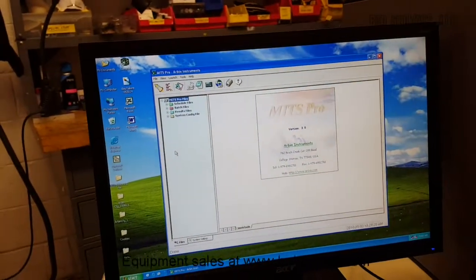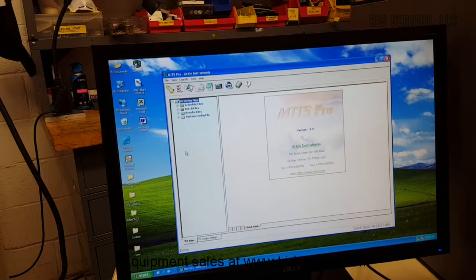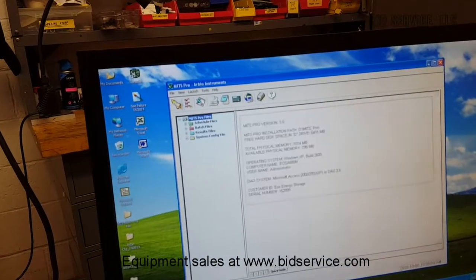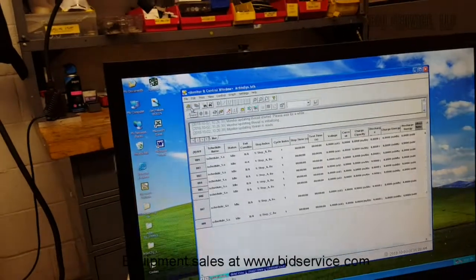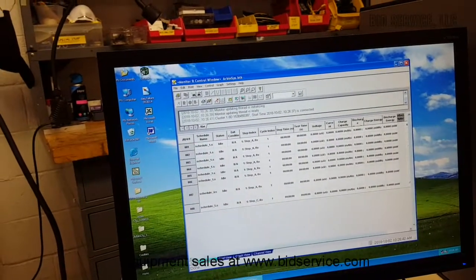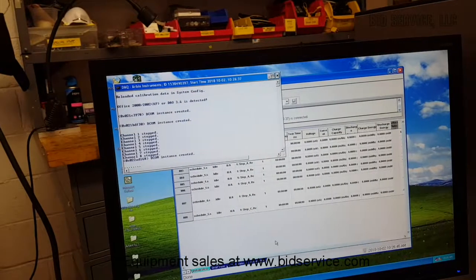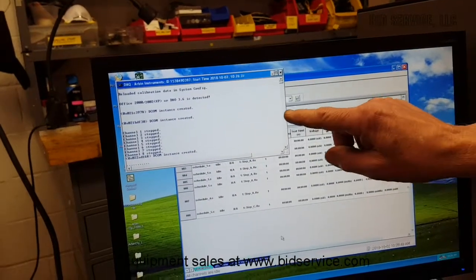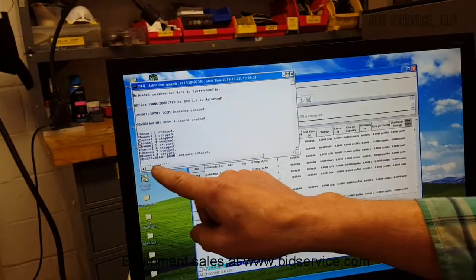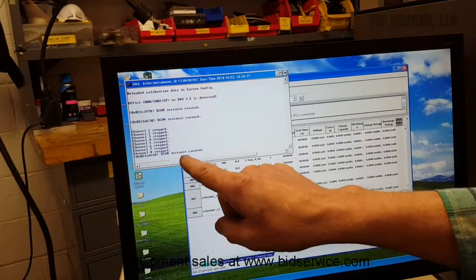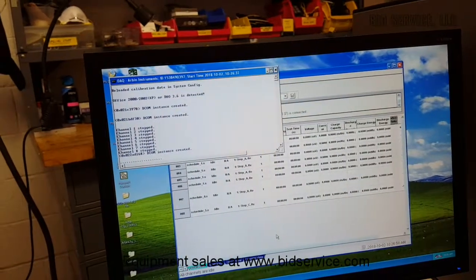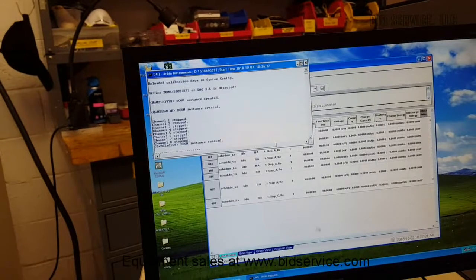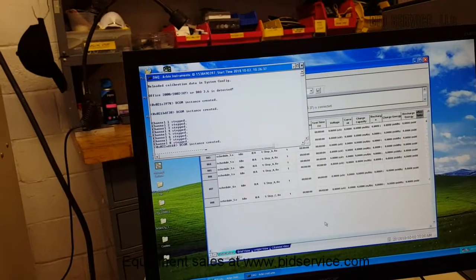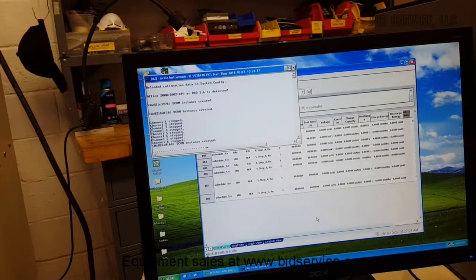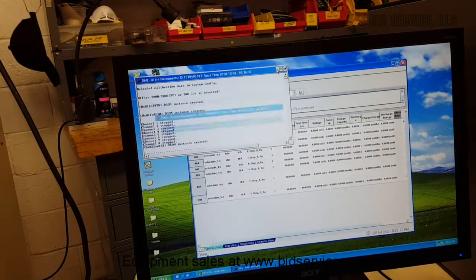Now, to actually launch your measurement software, there's a little space shuttle icon here that you would click on. And what that also does is it starts this window here. Now, this is your communication port. When you see that this is tracking along, instance created, you have communications with the Arbin system. If you should stop running the test, it would stop as well. So if you have a problem, just remember you have to launch before you do anything else. We'll put this away.